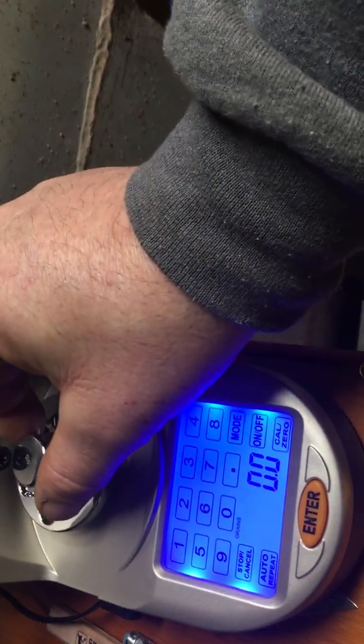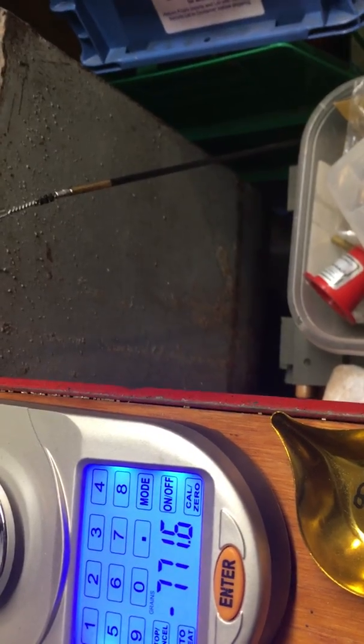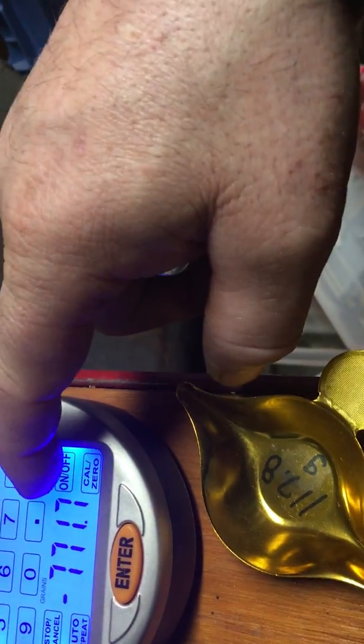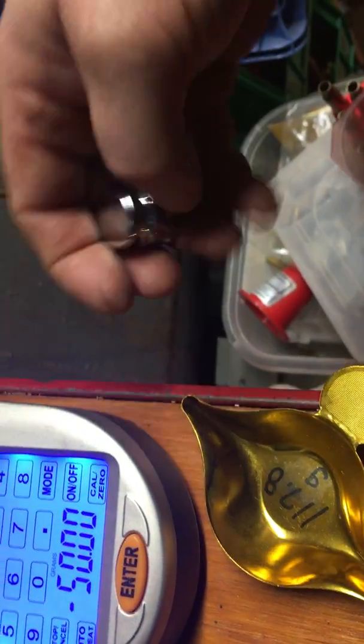It comes up at 77.16, and then I like to put it on grains. It says minus 500 — 500 grain weight — comes up dead zero. That's calibrated.